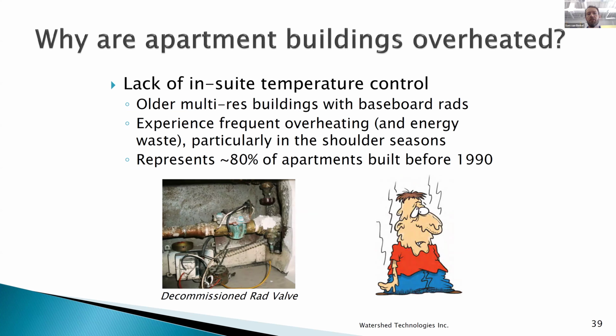So one of our main focuses in building automation is addressing overheating in apartment buildings. So as many of your members will know, the older multifamily buildings often have this issue where they're overheated, particularly in spring and fall. And this happens because a lot of these buildings don't have adequate in-suite controls. So some of them were built without any thermostats in the units, and some of them were built with thermostats, but often those thermostats over the years have been decommissioned. They're no longer functioning. So when there's too much heat delivered to the building, those units overheat, people open their windows, and your energy bills go up, and your money literally goes out the window.